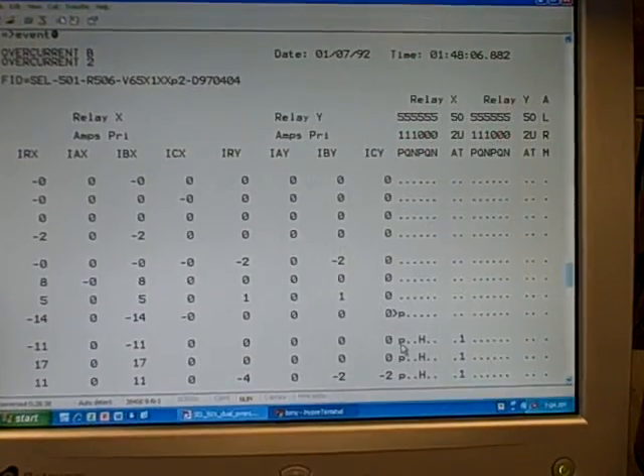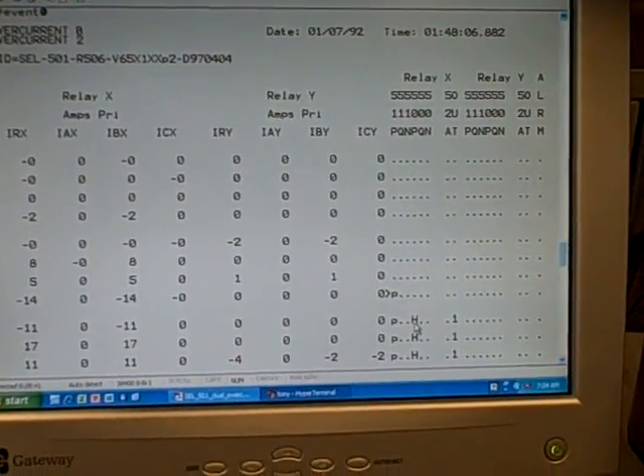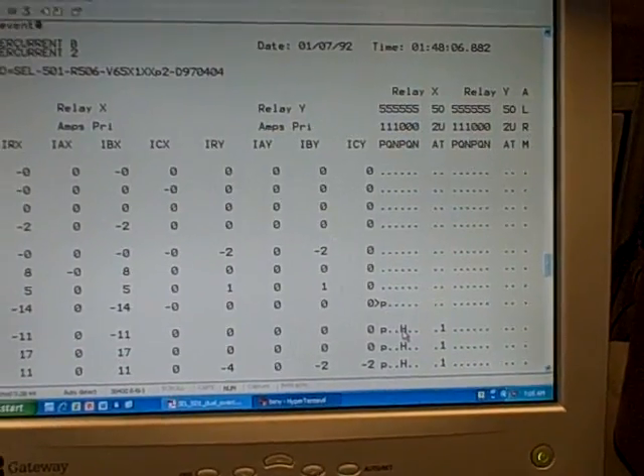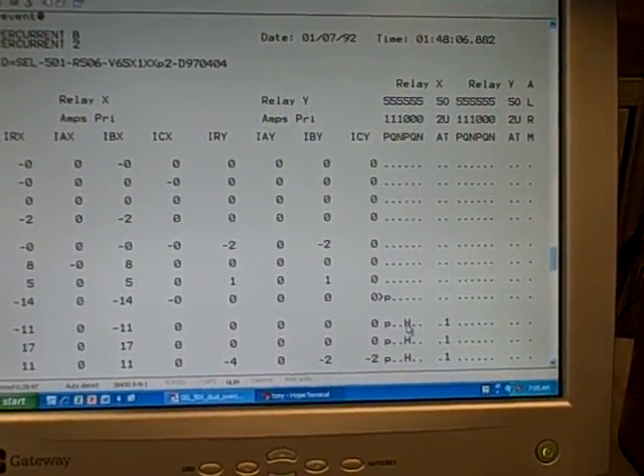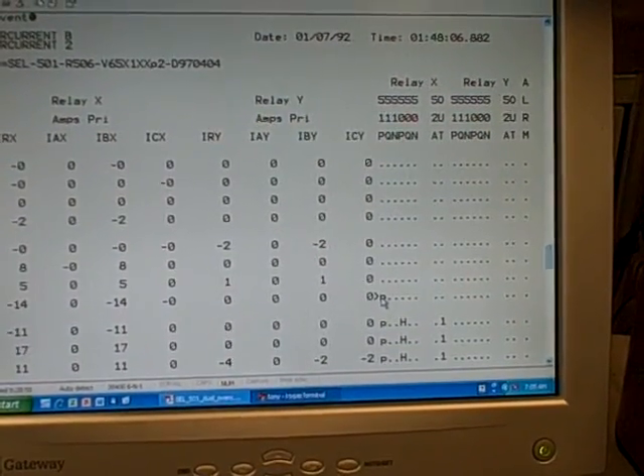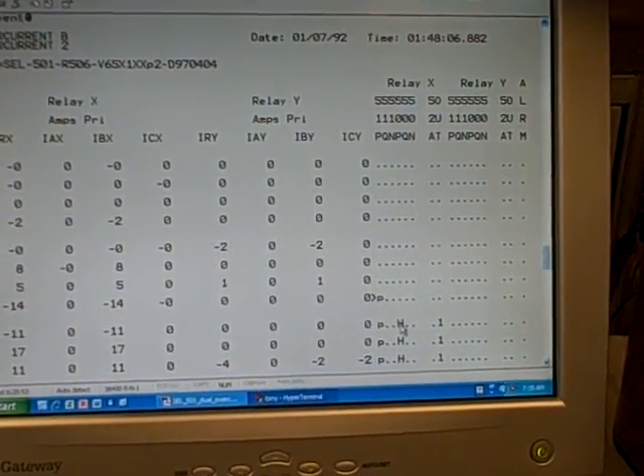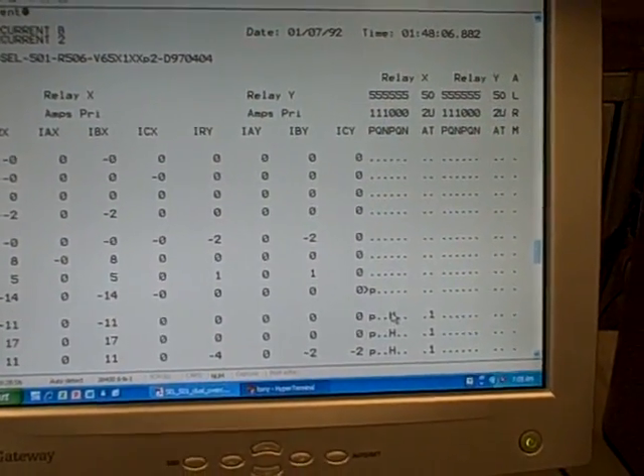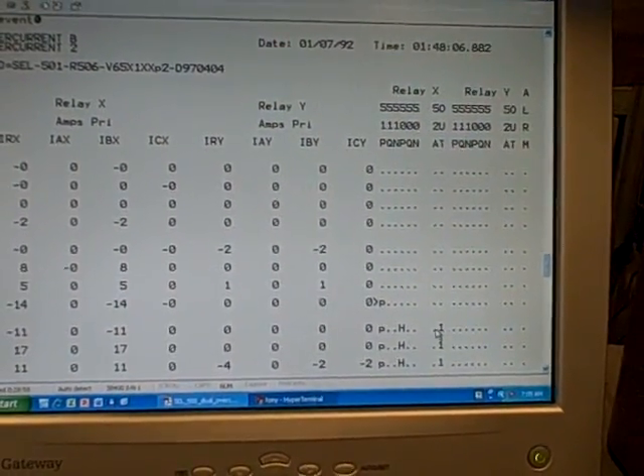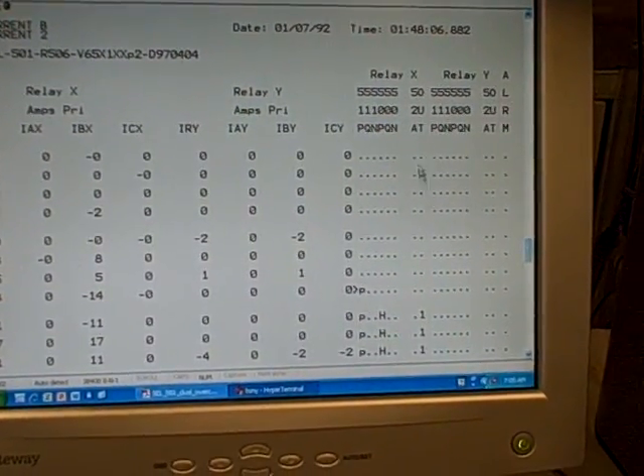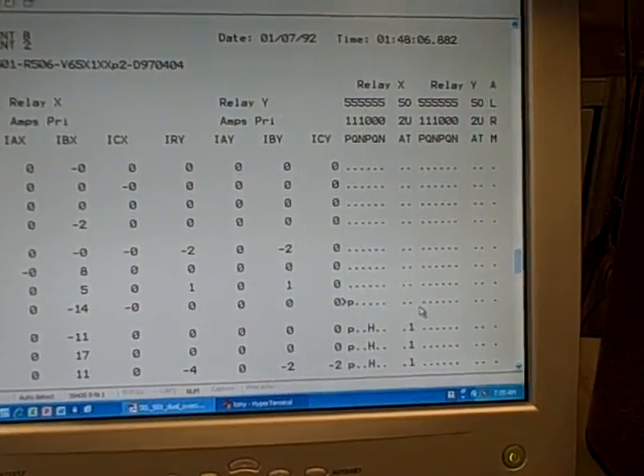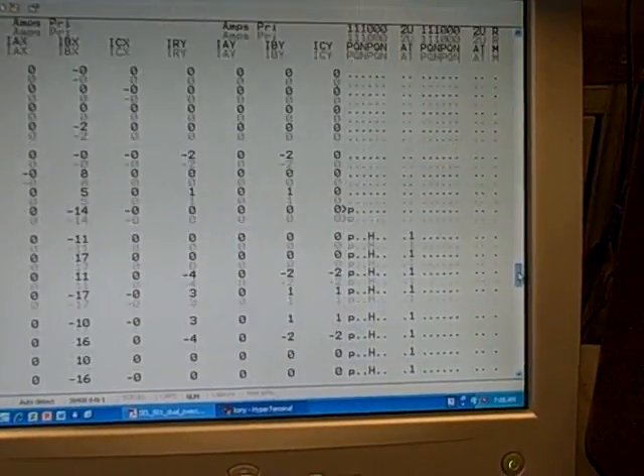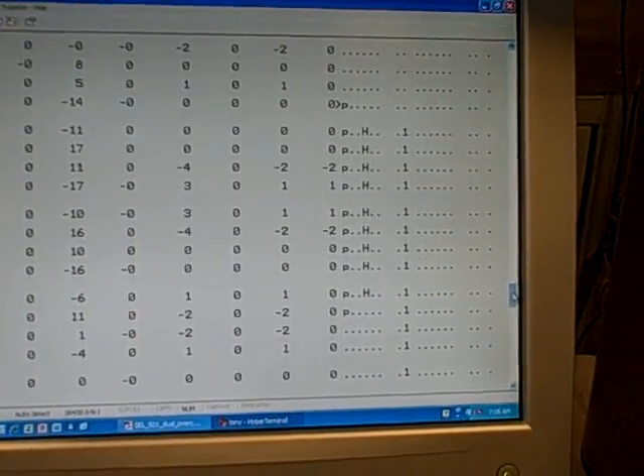Then over here, that's when our instantaneous, our 50P element picks up. That's because we set that to a secondary CT value of 4 amps, a primary value of 16 amps. So the 51 picked up, then the 50 picked up afterwards. Now because the 50P is an instantaneous, what that means is that as soon as it picks up, it trips the breaker. Immediately we see a number 1 appear under the output column. That's telling us that output contact number 1 has been asserted. We have initiated a trip command to the breaker.